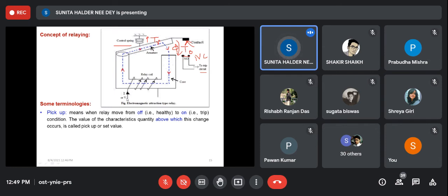Say the system current is 500 ampere, and the corresponding CT current is 5 ampere, and you have set the relay to operate at 5.5 ampere. So what is the corresponding system current? You can calculate. When the current is 5.5 ampere, that will also energize the flux such that the moving contact will move, but it will move slower as compared to when the current is 8 ampere, isn't it? For 5.5 ampere or for 8 ampere it will operate, but the speed of the moving portion will not be the same. For 5.5 ampere the speed will be slower as compared to 8 ampere, because the strength of flux will be lower in the earlier case. So beyond 5 ampere the moving portion will start moving.